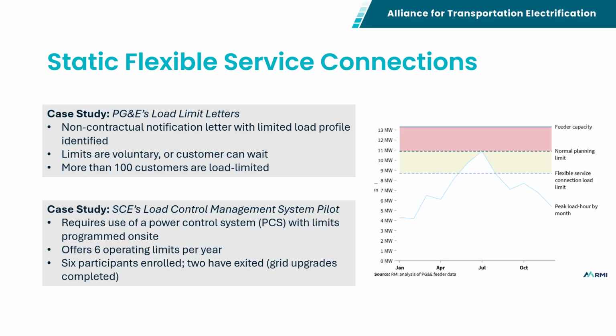So a customer comes in and says, I want 4 megawatts in this location. You can see that from the top of the peak load hour, looks like July there, to the top of the feeder capacity is only 2 megawatts. Normally, the utility would say, you can't have 4 megawatts. With a load limit letter, or with a phased service connection, they might say, you can have 2 megawatts now while we build the other 2. With a load limit letter, they would look and say, actually, we can give you all 4 megawatts most of the time. There are some times in the year that you will not be able to have all 4 and you will need to reduce down to 2 megawatts.